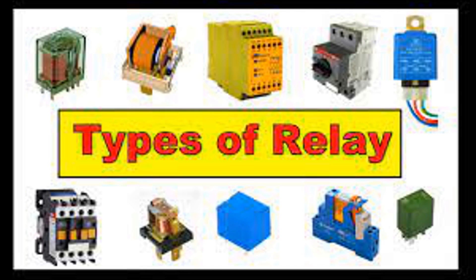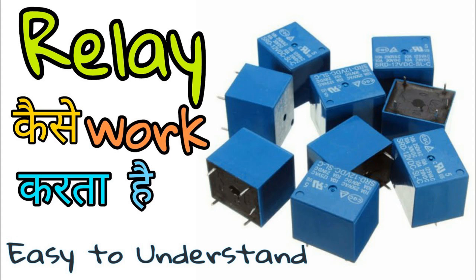Isolation, in the context of relays, refers to the separation of different electrical circuits to prevent undesirable interactions or disturbances. Relays provide isolation between the control circuit and the load circuit, and this isolation serves several important purposes. Protecting Control Components: The control circuit often involves electronic components such as microcontrollers, sensors, or low-power switches, which may be sensitive to high voltages or currents present in the load circuit. Isolation prevents these sensitive components from being directly exposed to the conditions of the load circuit.